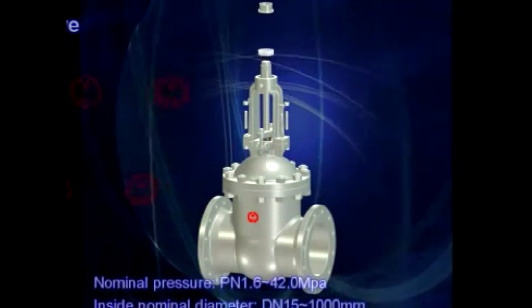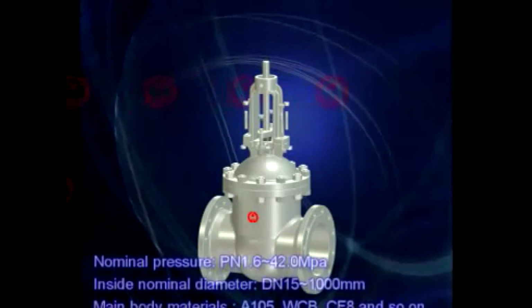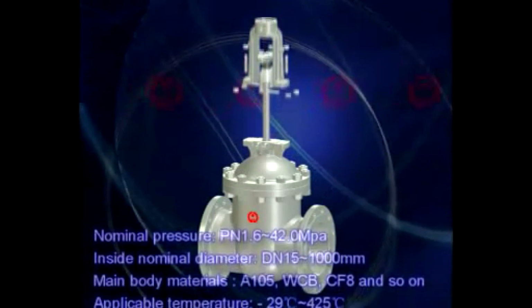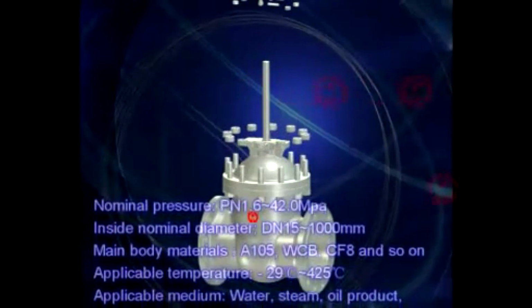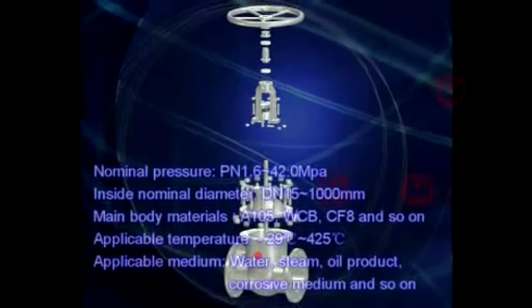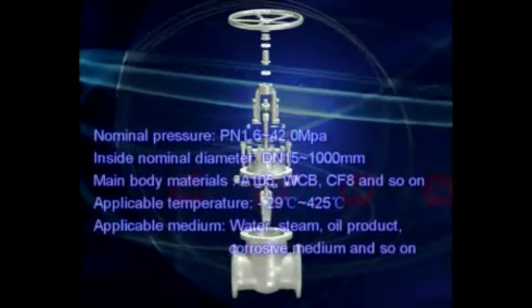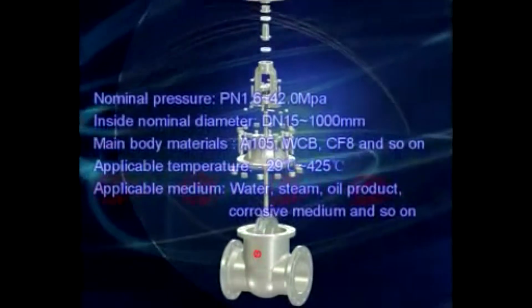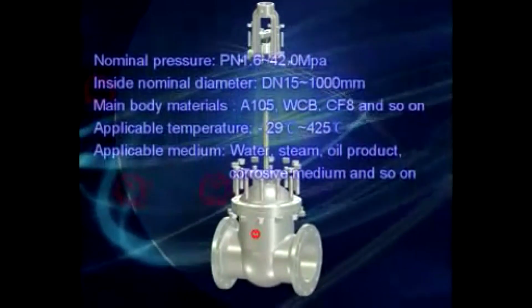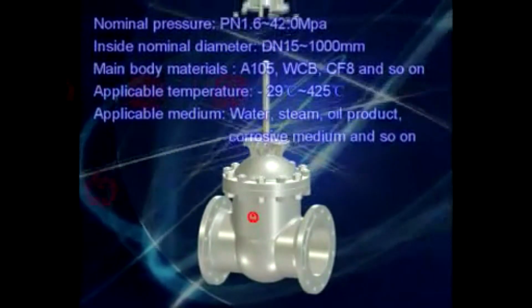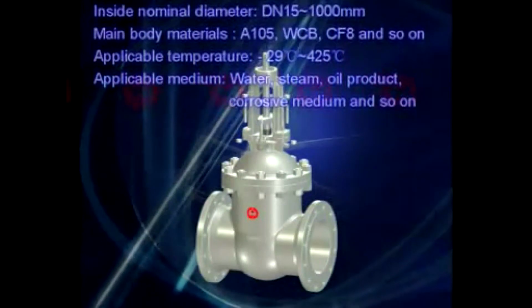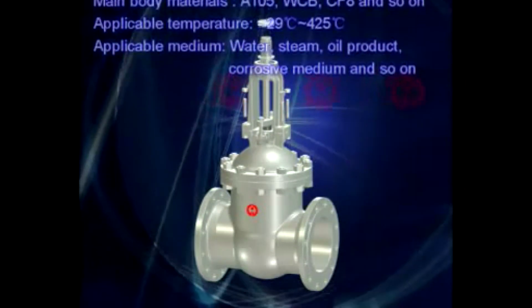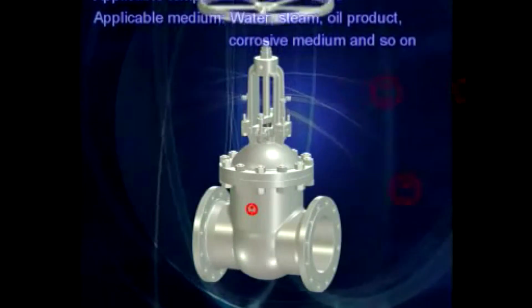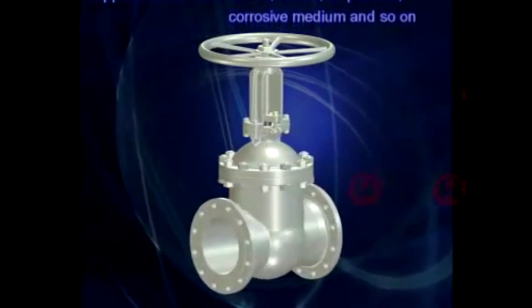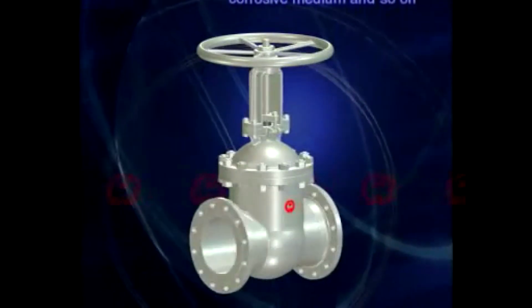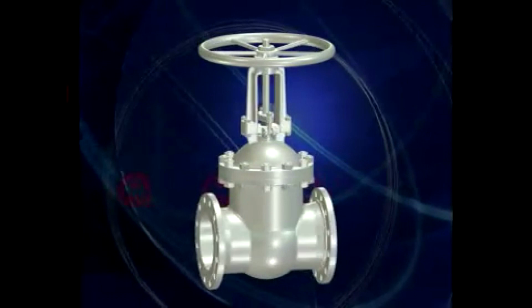Products designed and manufactured according to standard GB/T 12234-1989. Nominal pressure PN 1.6 to 42 MPa. Nominal diameter DN 15 to 1000 mm. Materials chosen for main body are A105, WCB, CF8, and so on. Applicable temperature from minus 29 degrees centigrade to 425 degrees centigrade. Applicable medium: water, steam, oil product, corrosive medium, and so on.